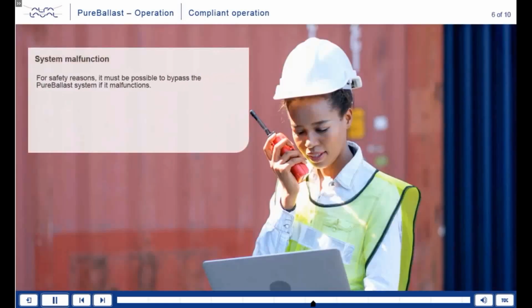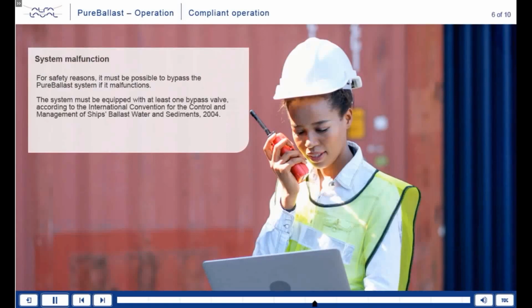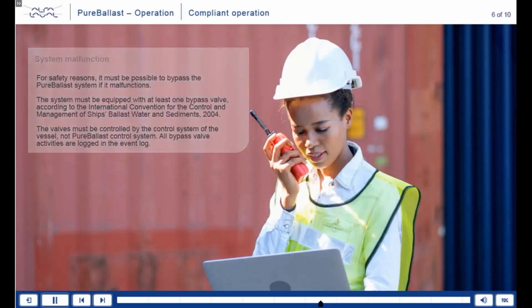For safety reasons, it must be possible to bypass the Pure Ballast system if it malfunctions. The system must be equipped with at least one bypass valve, according to the International Convention for the Control and Management of Ships' Ballast Water and Sediments 2004. The valves must be controlled by the control system of the vessel, not Pure Ballast control system. All bypass valve activities are logged in the event log.